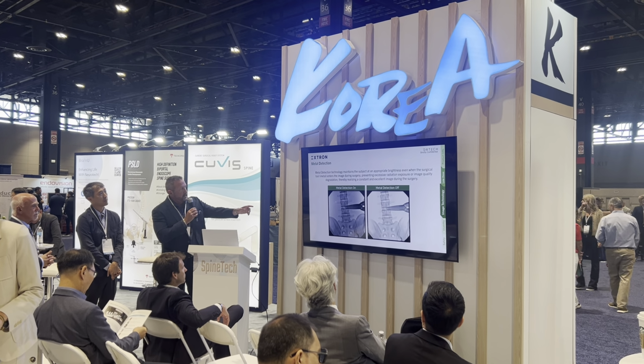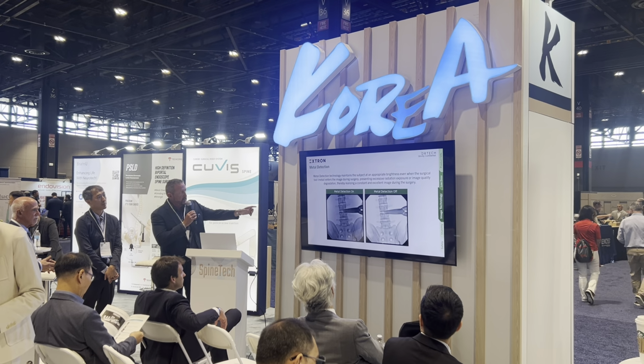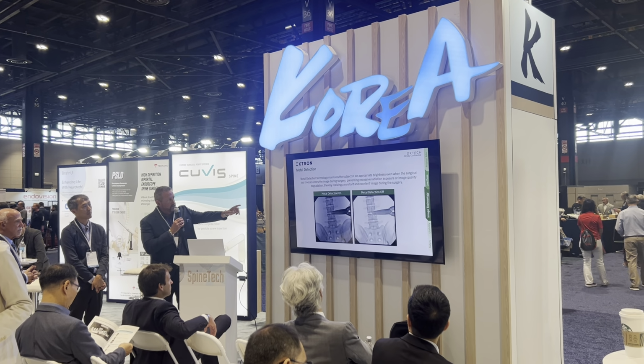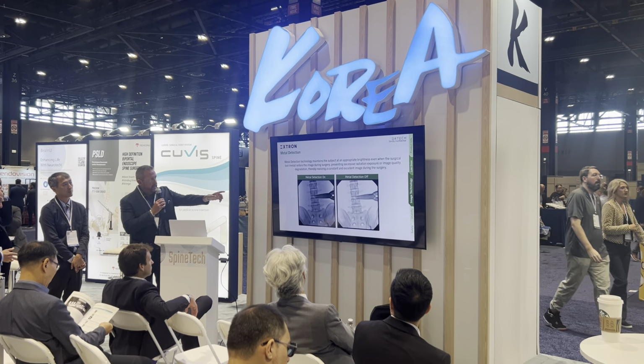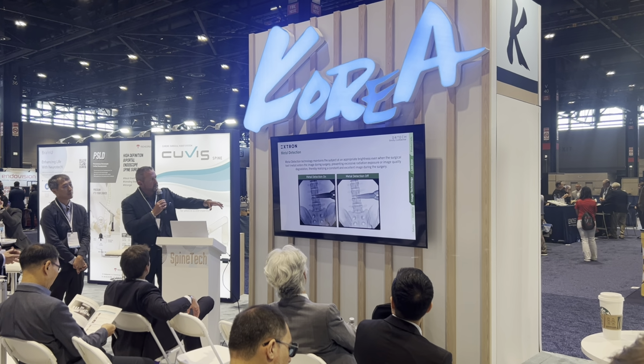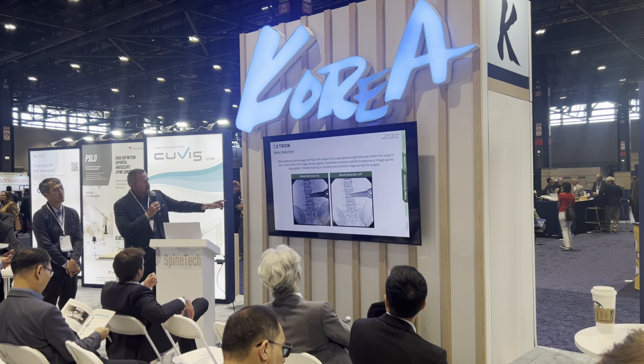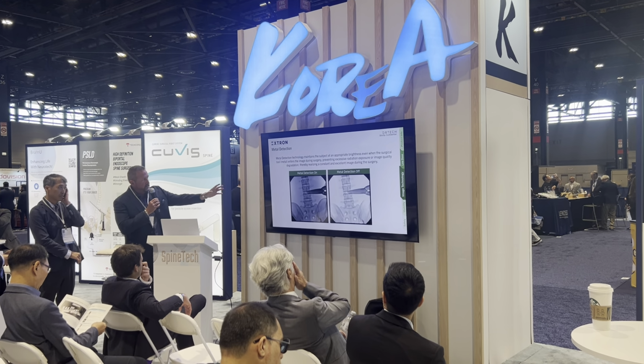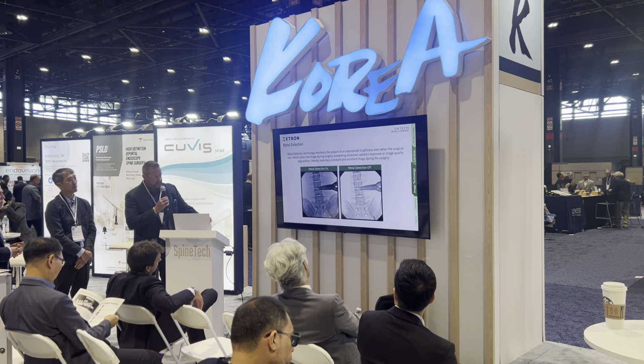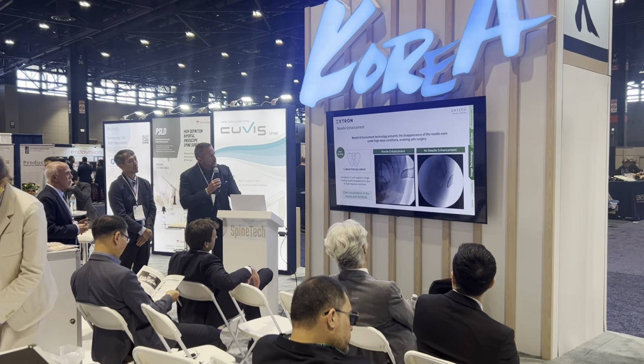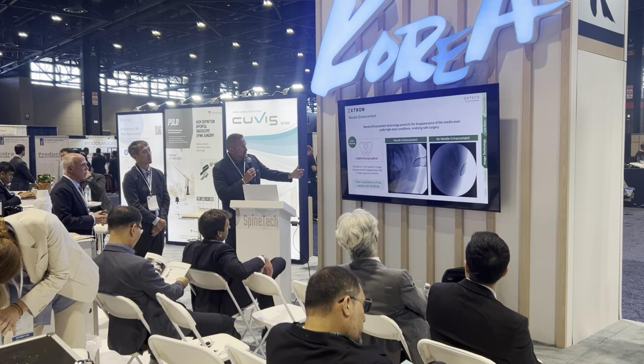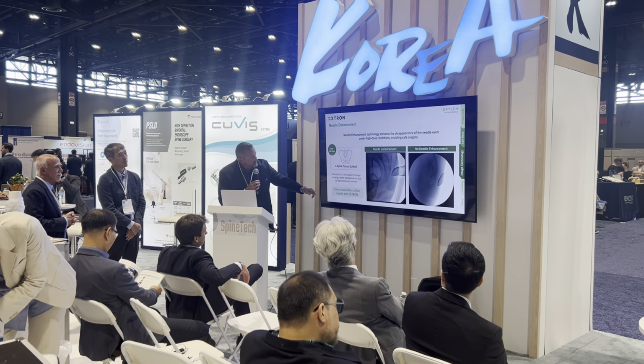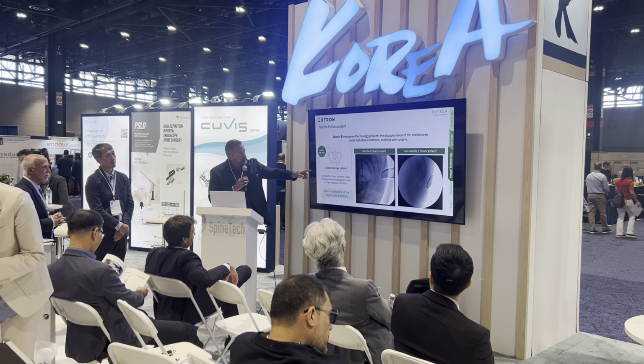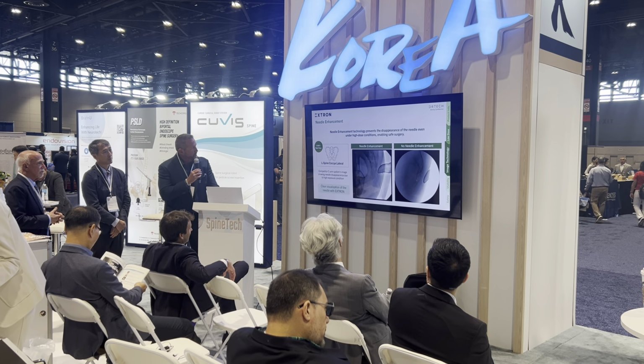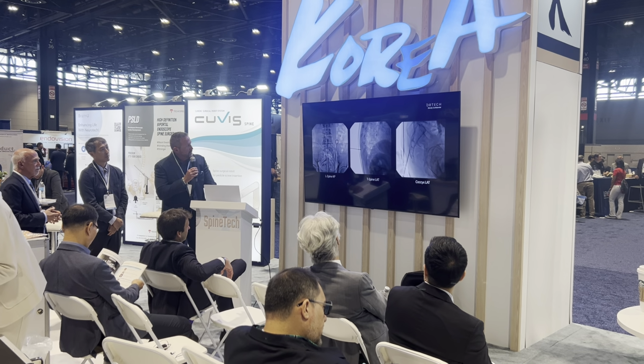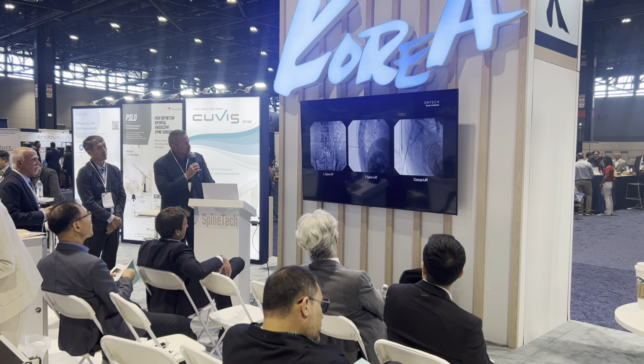This is metal artifact. On the right it's off, on the left it's on. So you see on the right, when you insert any metal, or if they have metal in the body, it will white out the image. On the left, with it on, it gives you a really clean image and it doesn't white out the image. Needle enhancement, it's kind of a funny picture, but you can see where the needle's at versus on the right with no needle enhancement. Again, more of the needle with it on.